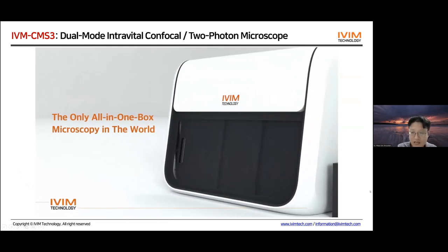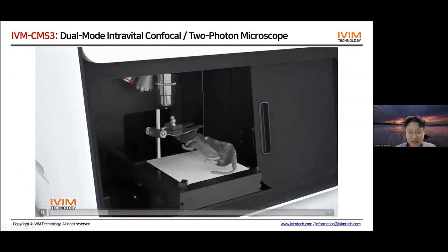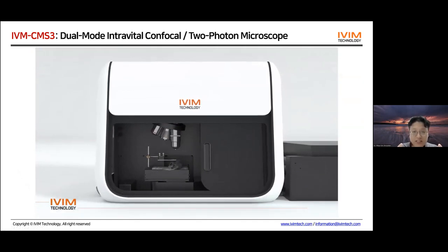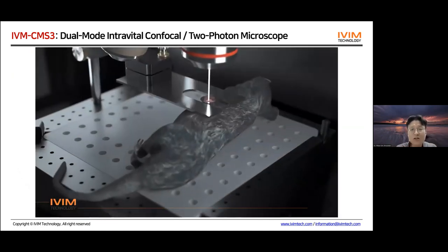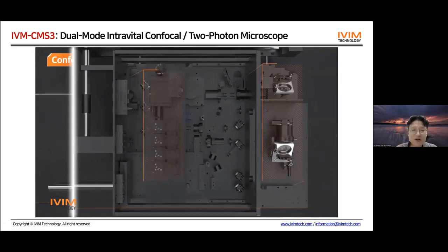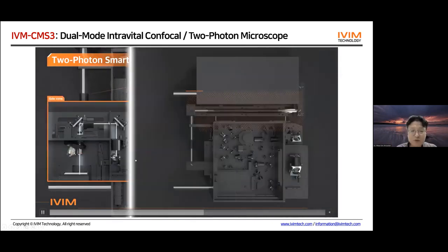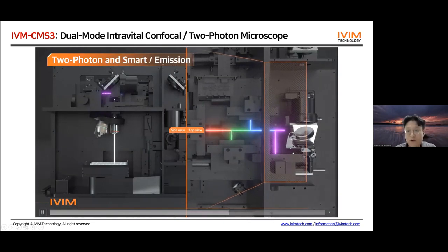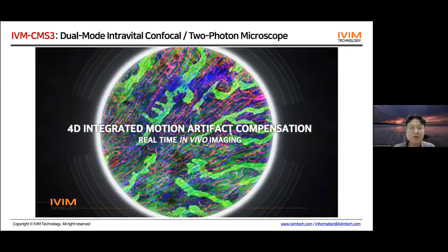This microscope can connect to additional laser systems. In the front we open the box and place the animal model on the animal stage for imaging. With this single-box packaging, you don't need a dark room, and it can be installed in a very small space. Inside, multiple optical components perform four-color confocal imaging and four-color two-photon imaging. We have two-photon lasers and four-channel NDD two-photon detectors for simultaneous four-color imaging in both confocal and two-photon modes.